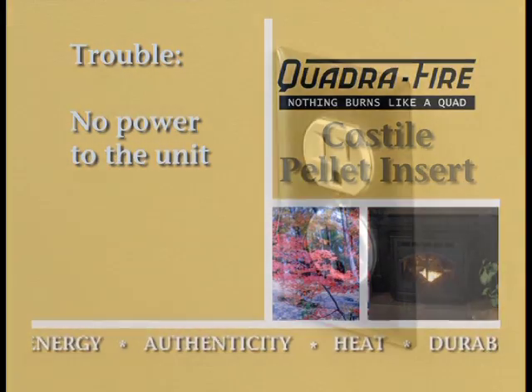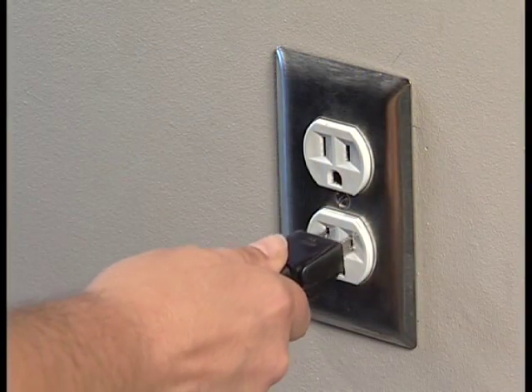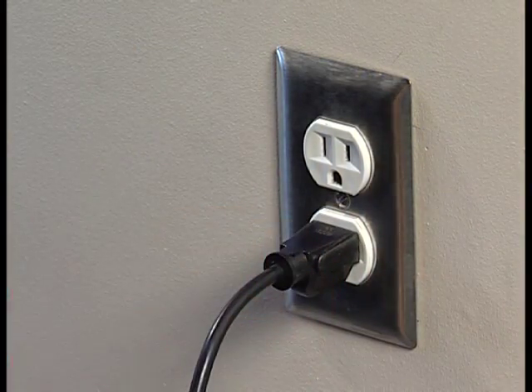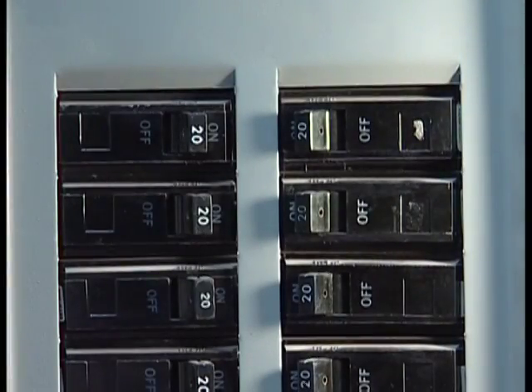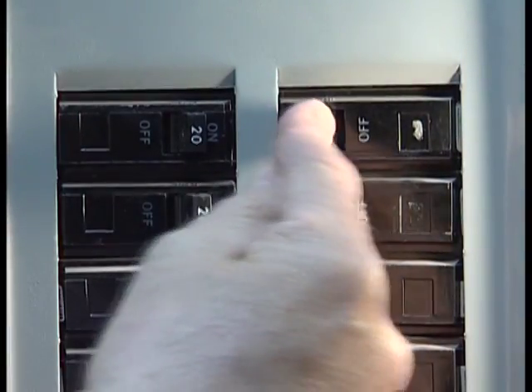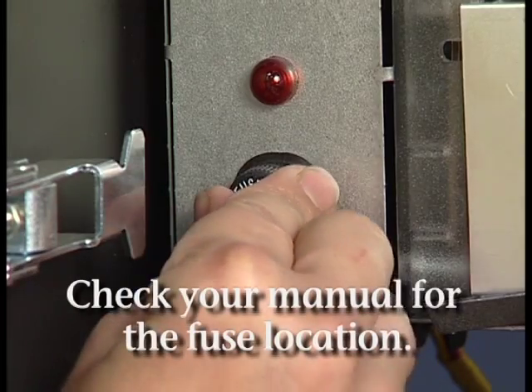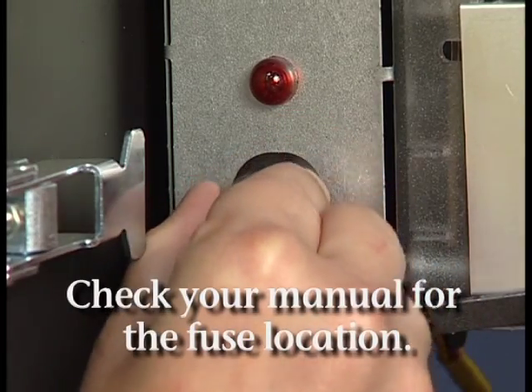No power to the unit. Check the power cord. Make sure it's plugged into the power outlet on the wall. Check the circuit breaker for the outlet and make sure it's not tripped. Check the 7 amp fuse on the junction box.